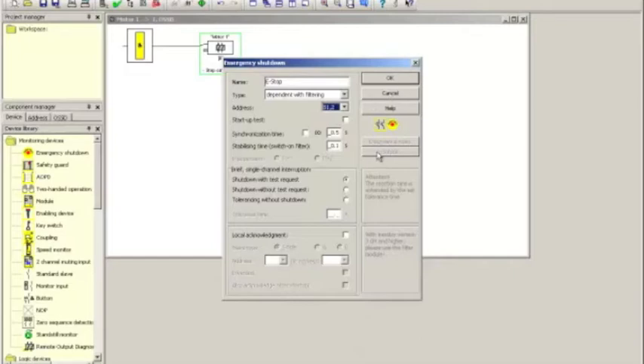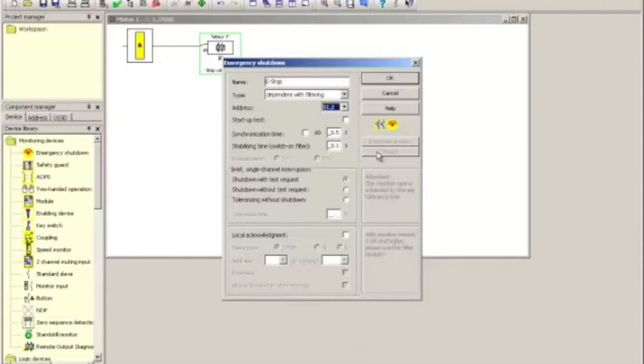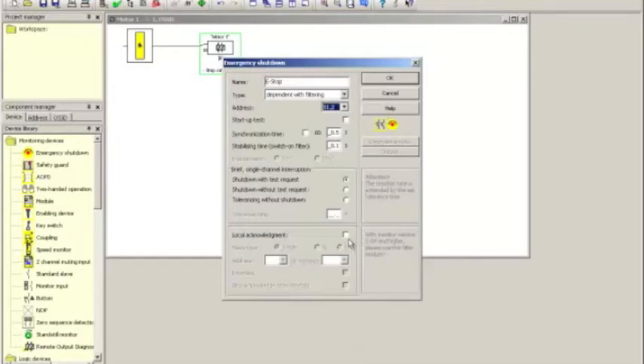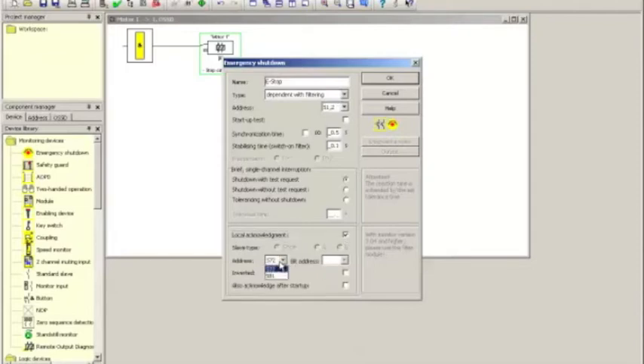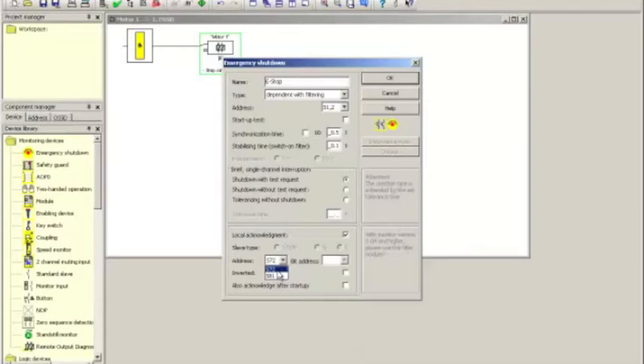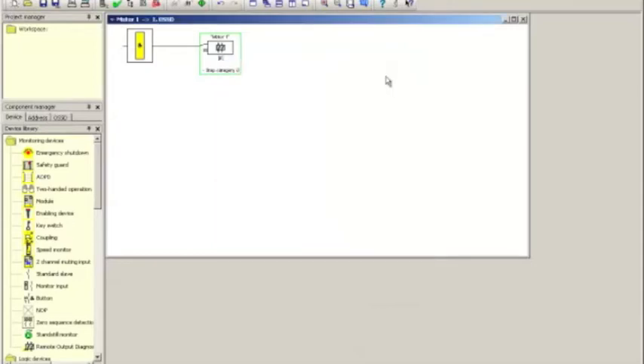And actually, there's one thing I want to do now. When using magnetic door switches, it is allowed that machines can auto restart when small access doors are closed. So we do not necessarily have to reset a system once one of those doors is open. As a consequence, I need to take the reset function and add it as a sub function to the e-stop. I do that by clicking on the local acknowledgement. And from this window, I select which of the conventional inputs is used as my reset function. And S7-2 is where my reset button is connected, so I will pick that one. That's all I have to do. And I click OK to close this out.